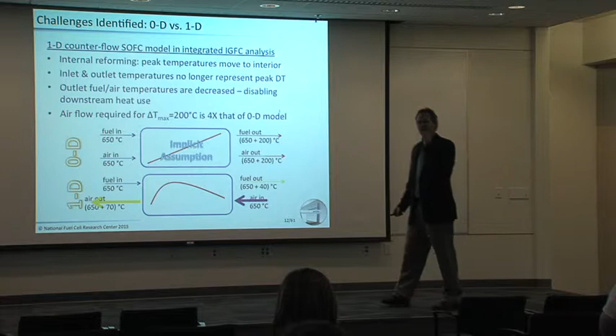And this is what happens to the analyses. This is looking at all of the major performance characteristics, like how much energy is coming from my steam turbine, from the expander topping cycle, how much from the fuel cell, electrical power, etc. What you see is that with more air going through my system, I get a little more cathode expander power, a little more total gross power made, but I have a huge increase in my SOFC blower compressor. So to push all that air through my system, overall efficiency drops from 61% to 45%.